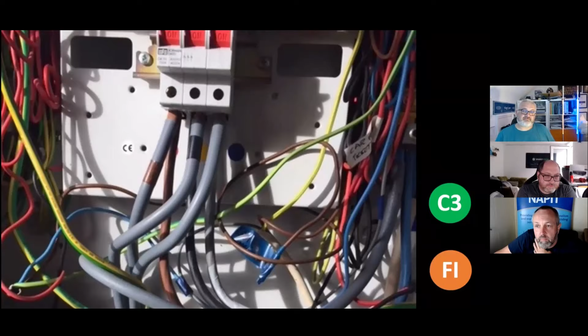It's the daisy chain effect of 3-phase boards. You get a lot of distribution where, rather than design it and do a proper job, it's daisy chain board off a board off a board off a board. And what you'll end up finding is, say you go into a car park and do an earth loop test at a lighting column, you may find the earth loop impedance is too high, or you don't even have sufficient fault current to disconnect the breakers feeding it.